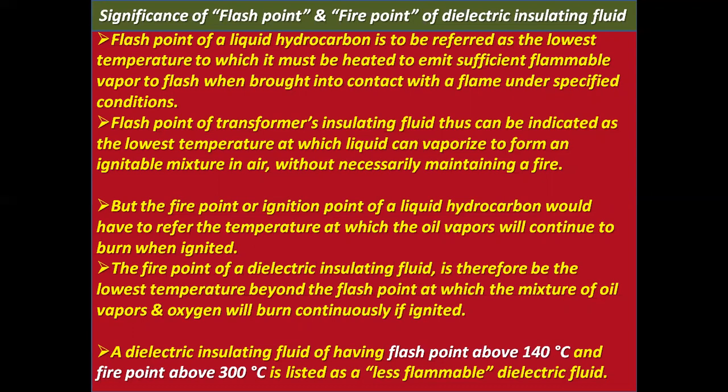Flash point of transformer's insulating fluid can thus be indicated as the lowest temperature at which liquid can vaporize to form an ignitable mixture in air without necessarily maintaining a fire.